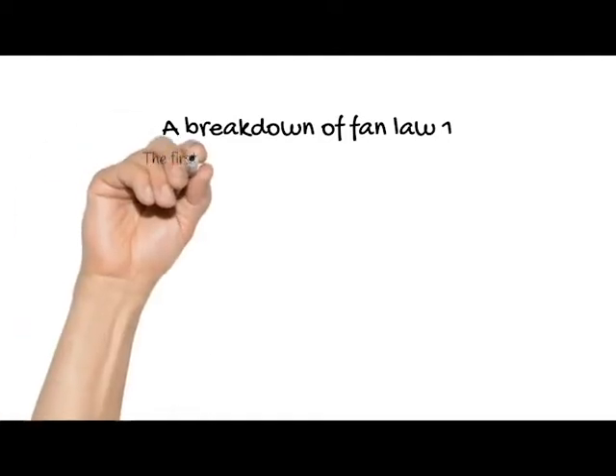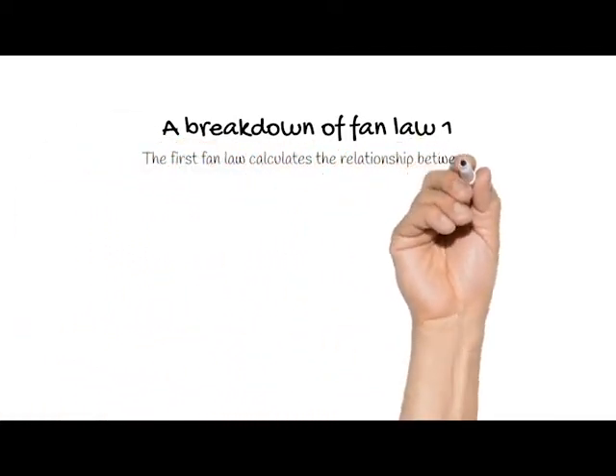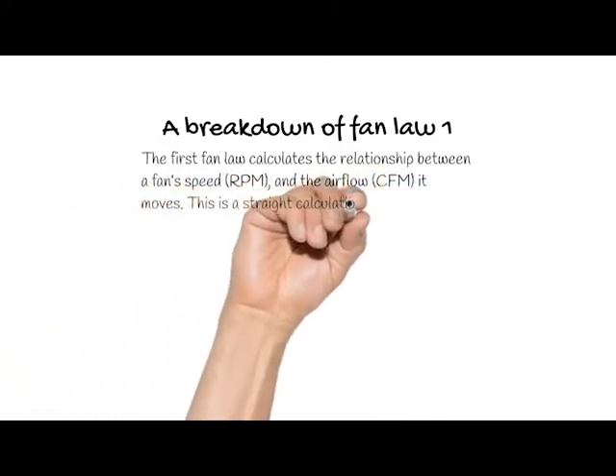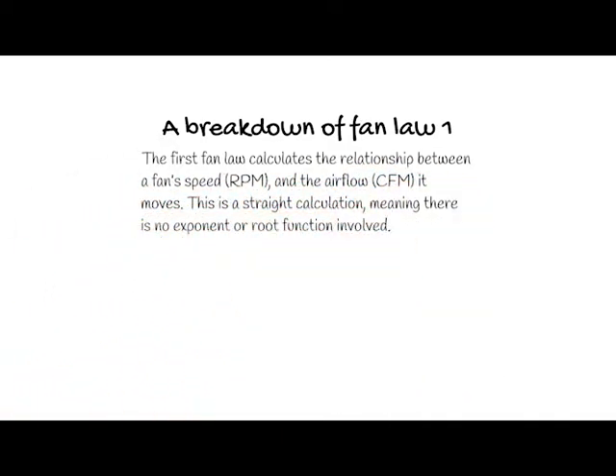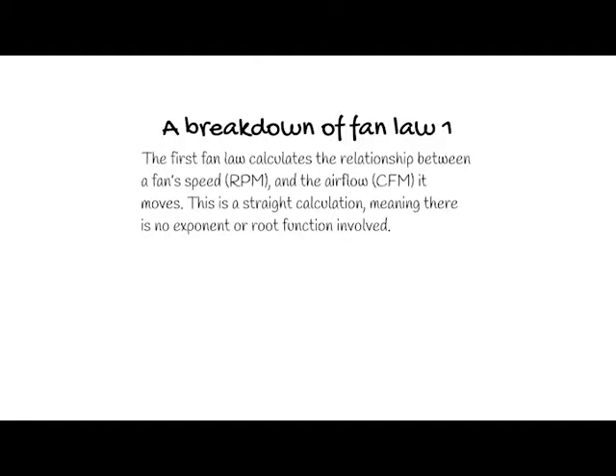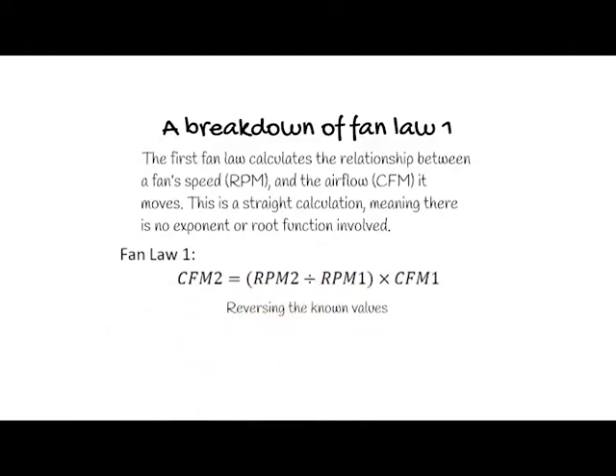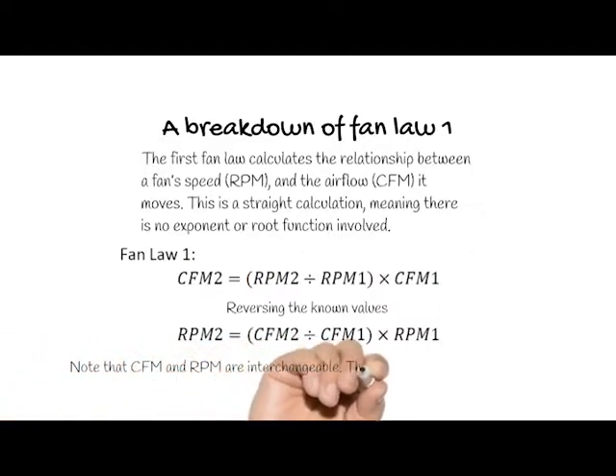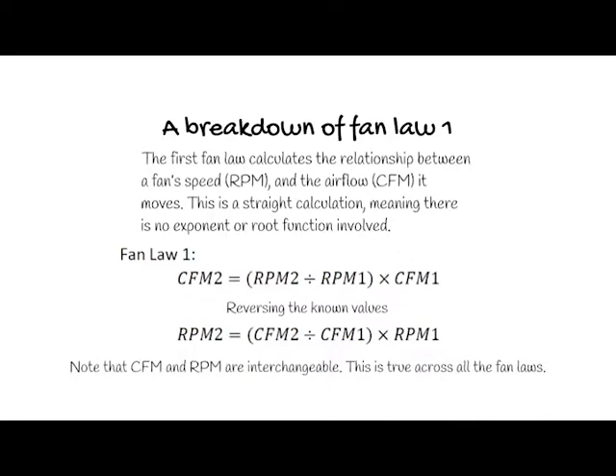Let's break down fan law 1. The first fan law calculates the relationship between a fan's speed and the airflow it moves. This is a straight calculation, meaning there is no exponent or root function involved. Fan law 1 states that CFM2 equals RPM2 divided by RPM1, times CFM1. If we reverse the known values, RPM2 equals CFM2 divided by CFM1, times RPM1. Note that CFM and RPM are interchangeable, and this is true across all the fan laws.